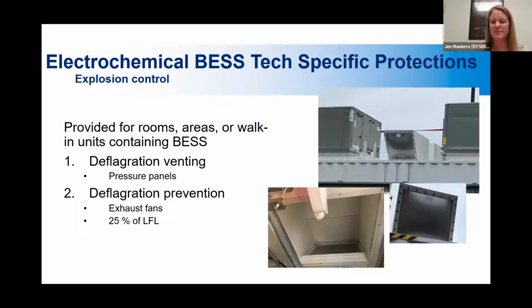Explosion control. I've touched on this a couple times because I know it's a very hot topic. Deflagration venting is those pressure panels that I've mentioned a few times, and you can see them in the images on the right. And again, they're designed so that if there's enough buildup of gas and pressure in the enclosed space, they can direct an explosion out to where it is not going to hit people. For example, like we saw in Arizona a few years ago, you don't want any explosions coming out the doors where first responders might be trying to enter. If there's going to be an explosion, you want it directed in a place where nobody's going to get hurt, and that would most likely be on the top of the containers, right?